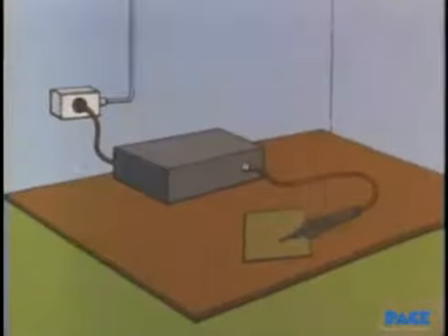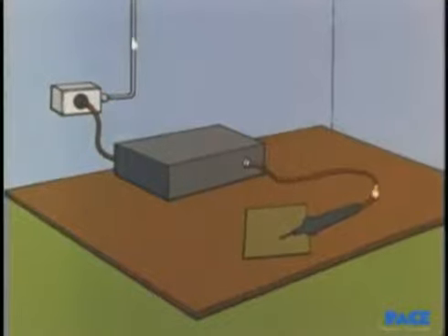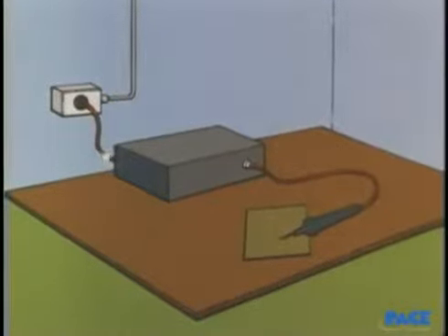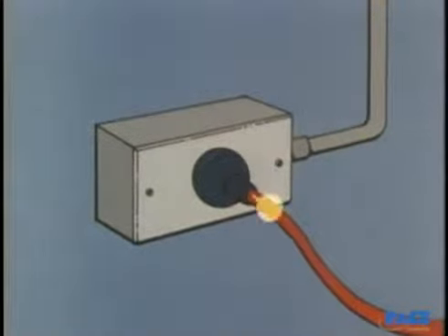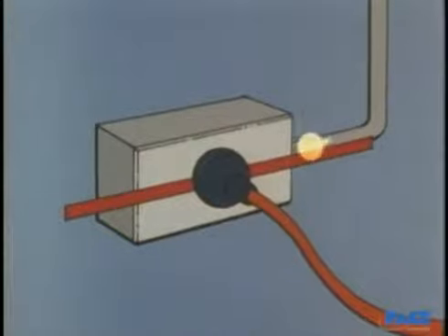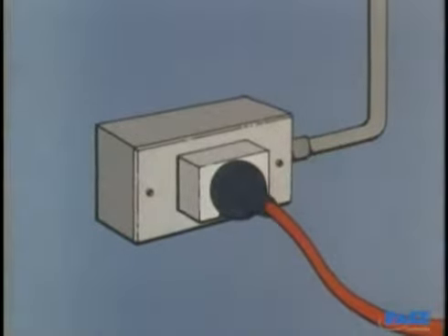Another source of the problem can be the power line itself. Brush motors, relays, and any non-zero powered switching equipment may be connected to the line somewhere else in the building. They generate spikes and could be injecting them into the power system. They come down the line, pass through your equipment, and right into the board, even though your equipment has zero power switching. The place to stop this is back here, between your equipment and the power line. And the way to do it is by putting the proper filter between the two. Even better, and if possible, prevent the power line from becoming contaminated in the first place.